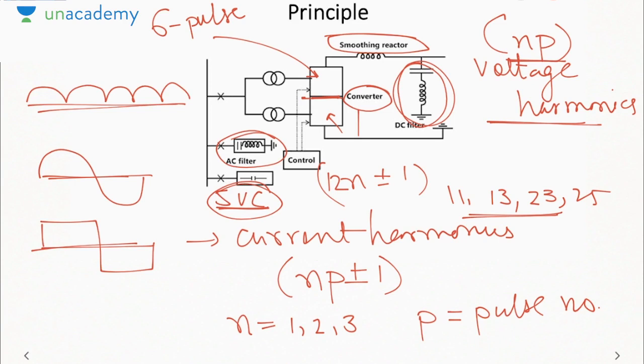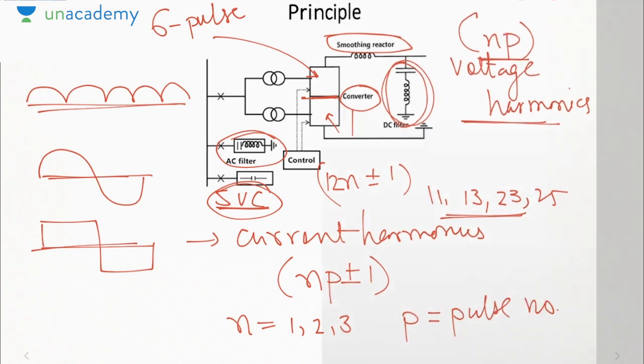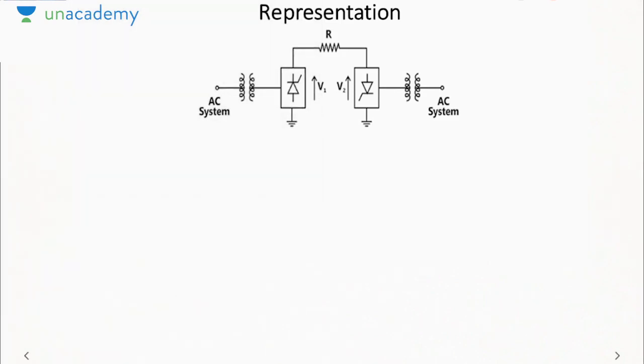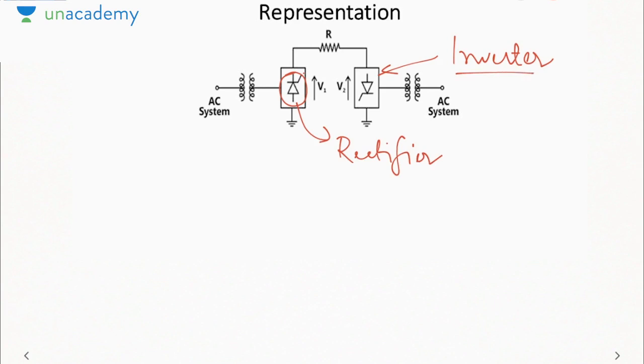But the advantage of DC is power will always flow from higher voltage to a lower voltage regardless of the angle, because in DC there is no concept of phase. There is no phase angle. So power will always flow from higher DC voltage to lower DC voltage. And the DC voltages of inverter and the rectifier can be varied by varying the firing angle or the extinction angle. Like here, if I represent this HVDC system by this, an SCR pointing upward always represents a rectifier. An SCR pointing downwards represents an inverter. Okay, so power will flow from rectifier to the inverter.